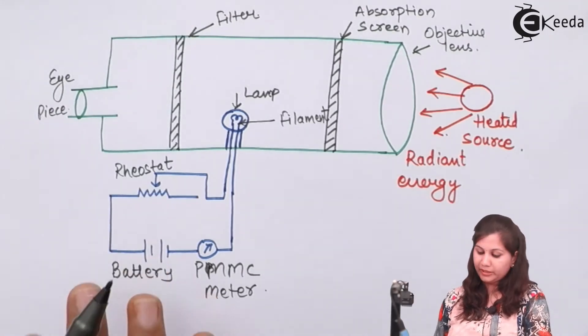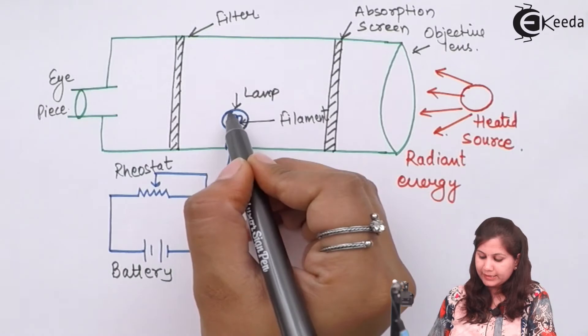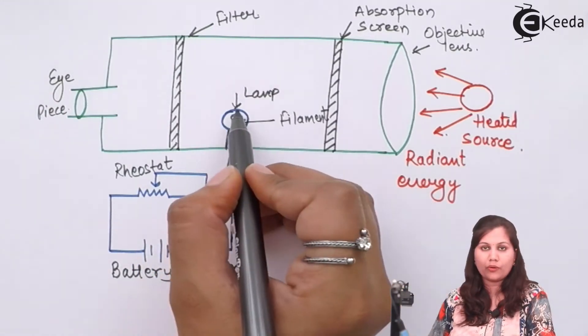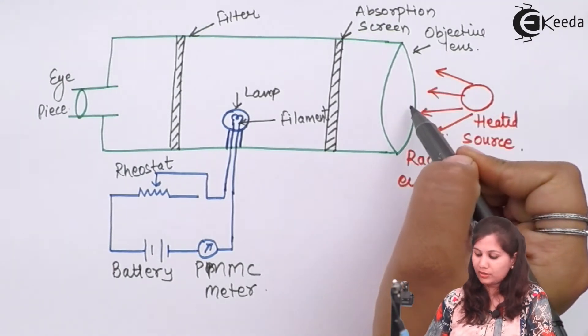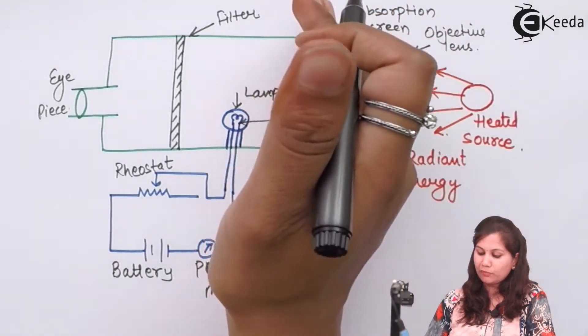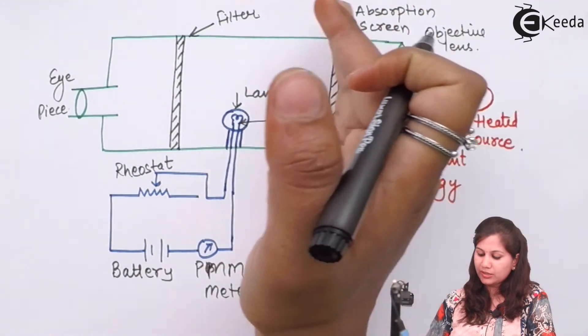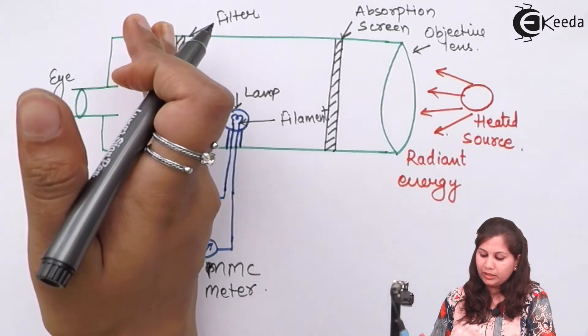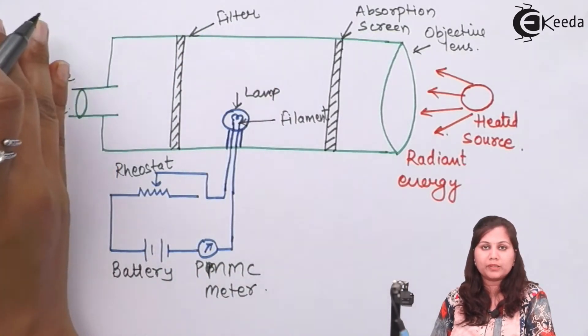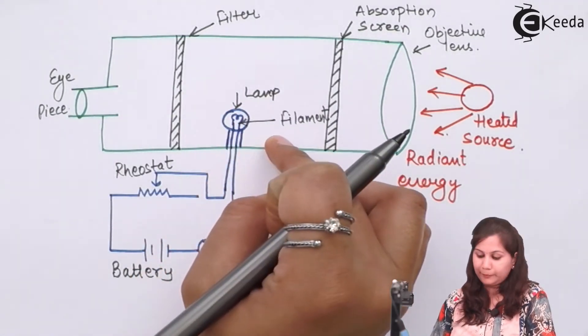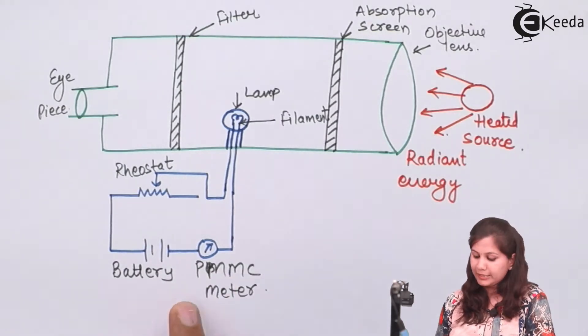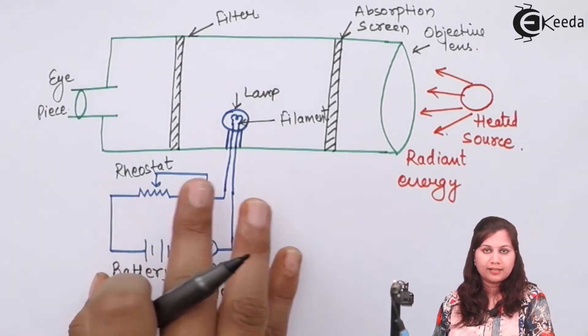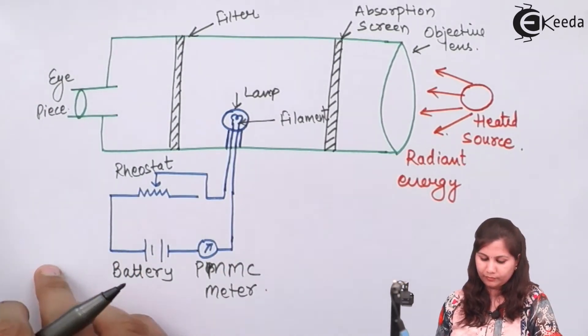This is the disappearing filament optical pyrometer. Here we have the filament inside a lamp, and we measure brightness by comparing it with this lamp. The heated source emits radiant energy. These radiations are absorbed by an absorption screen, then compared with the brightness of the filament. After passing through the filter, it reaches the eyepiece where the observer views the filament. The electric circuit connected to the filament consists of a rheostat, a PMMC meter, and a battery. The PMMC meter measures the current flowing in the circuit.